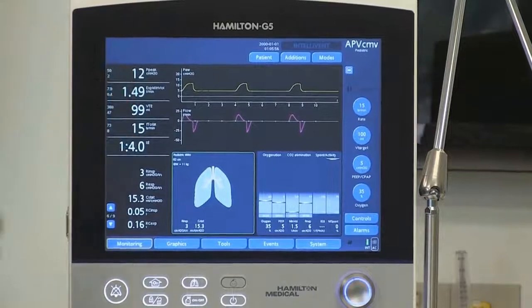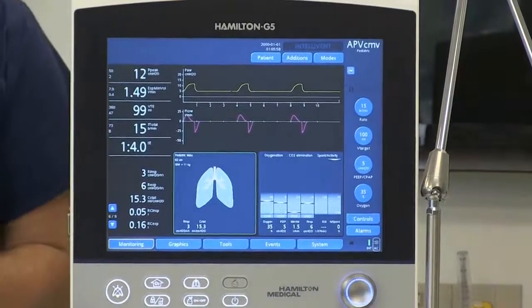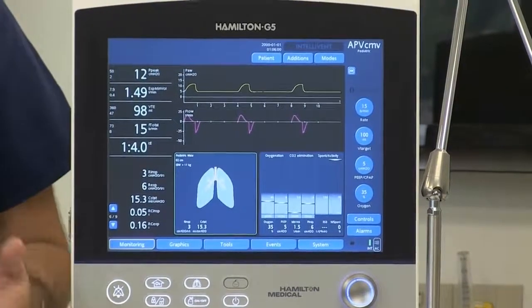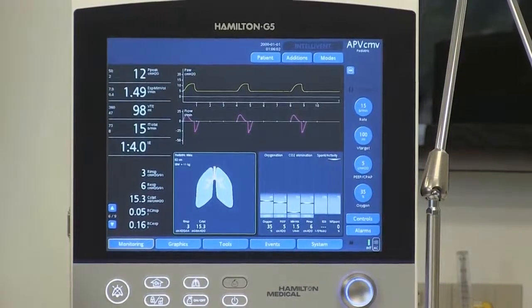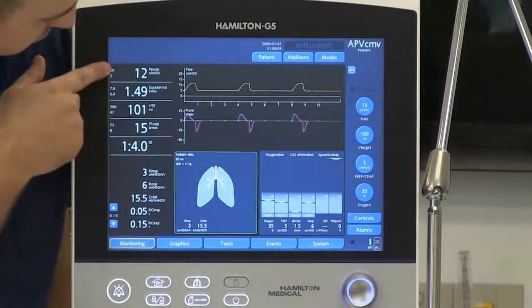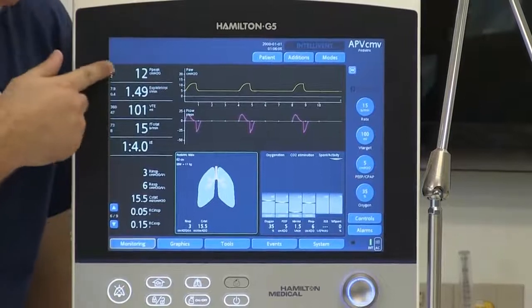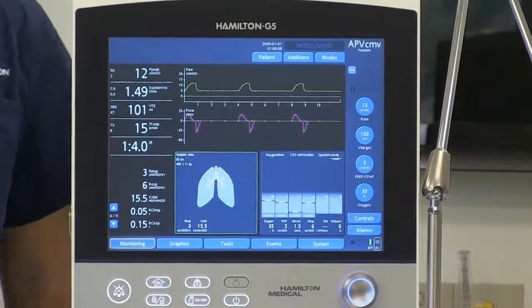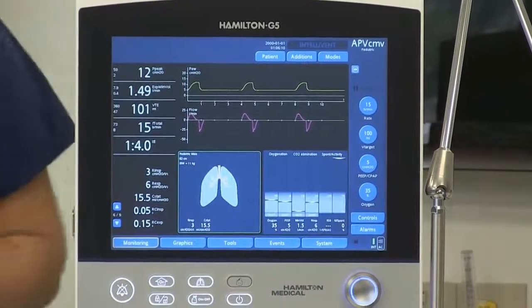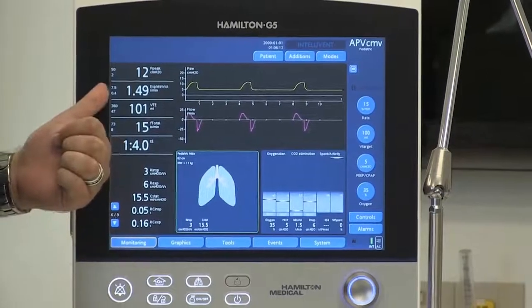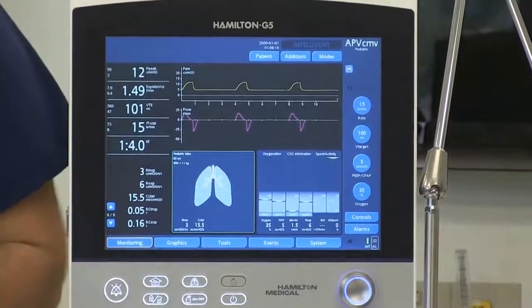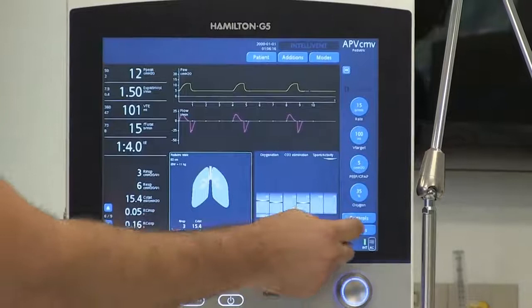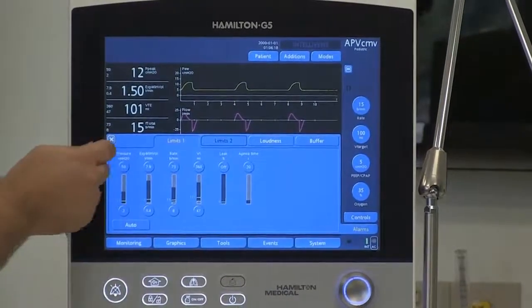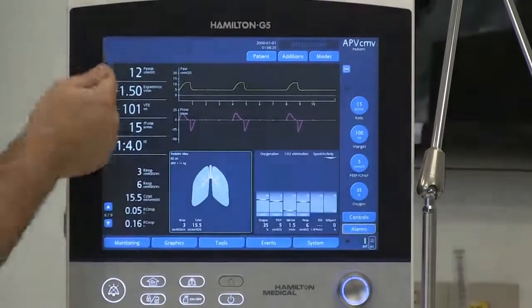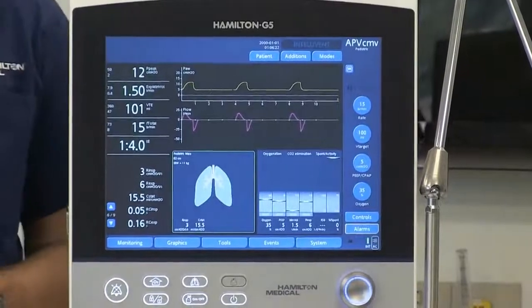Up here is your measured parameters. We can configure them to whatever parameters you most normally use to monitor. I would like to bring your attention to these tiny numbers here to the left of your main monitor parameters. And those are your alarm limits. So you actually don't have to go into the alarms tab to see what your limits are. They are printed right here on the left.